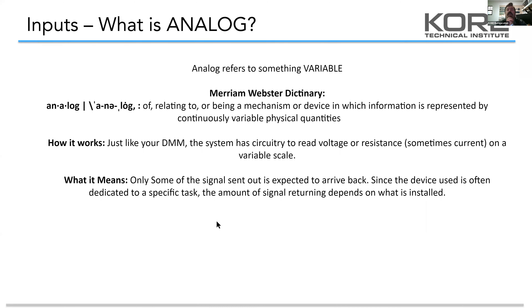Now let's talk about analog inputs. Analog simply means variable — something that throttles or varies from a minimum to a maximum. The two types of analog inputs we're going to see a lot are either temperature, where we're using thermistors — most manufacturers use thermistors, and some use a variant like RTDs — and the other type of analog input are transducers, where you're going to get your pressures, humidity, liquid levels, leak detectors, light levels, and currents.